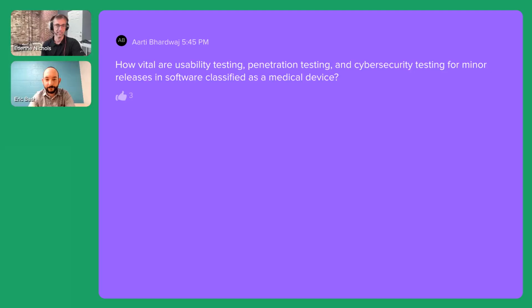So, Aarti, if I'm saying your name correctly, asked, how vital is usability testing, penetration testing, and cybersecurity testing for minor releases in software classified as a medical device? It's kind of a loaded question. Generally, the FDA's stance on patching is if you're making a patch for safety or cybersecurity purposes, it is held to less rigorous standards than if you're making a patch for other reasons. The idea being that you've done some sort of risk-benefit analysis and you don't foresee significant issues caused by this patch. You've done some sort of limited testing to show that the patch doesn't break everything.